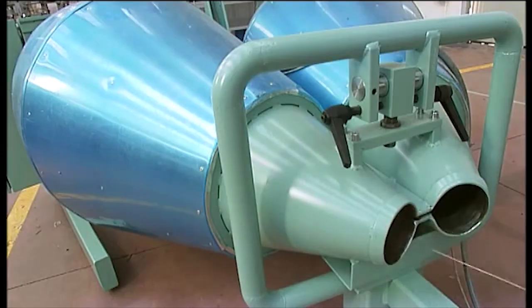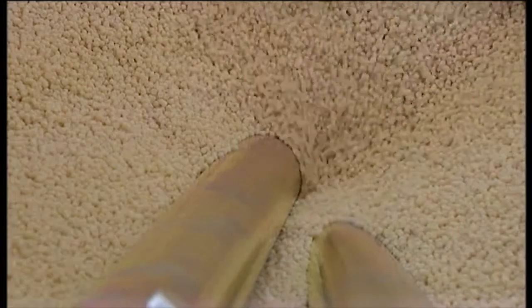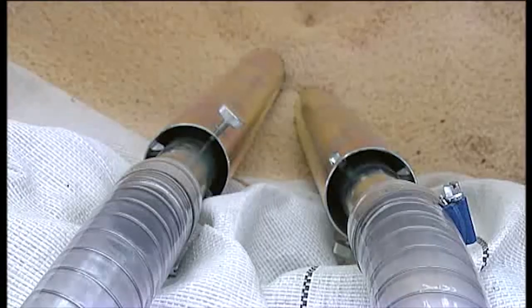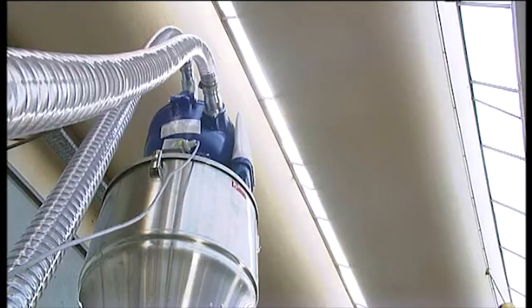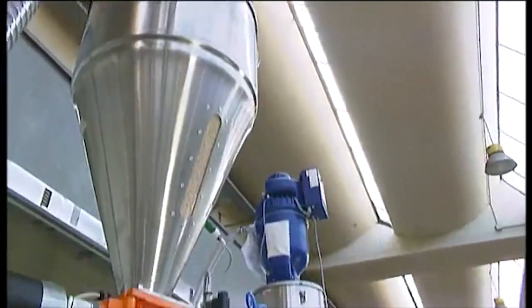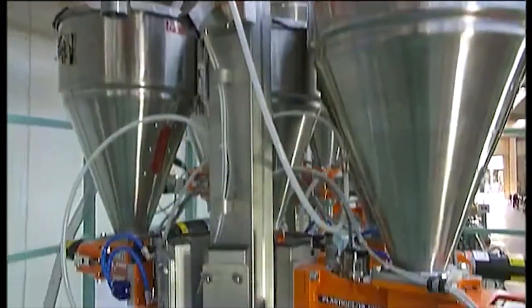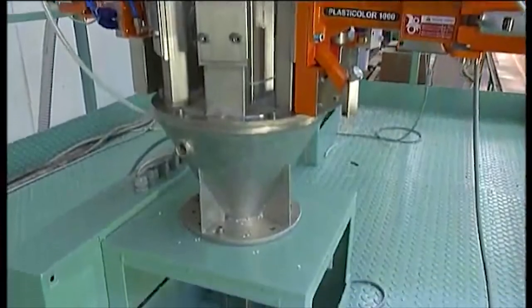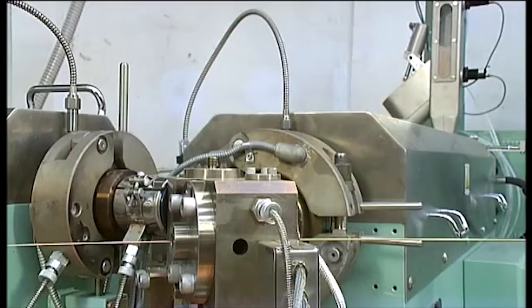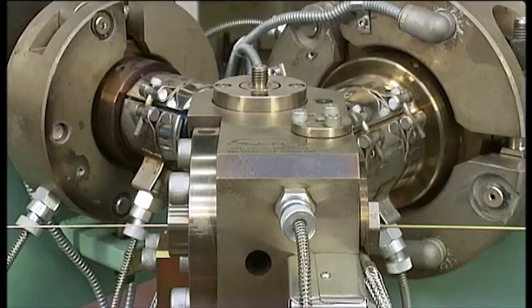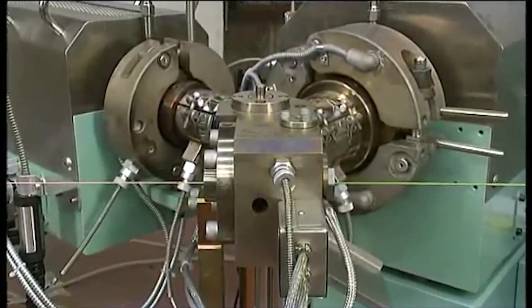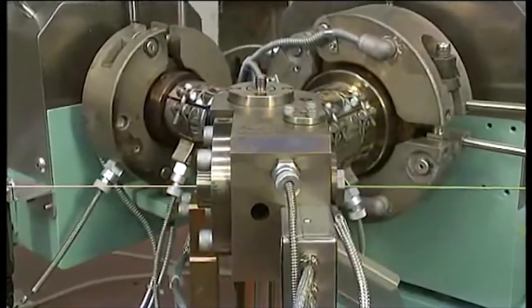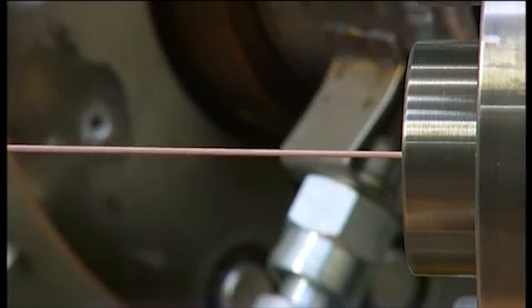The PVC insulation is done in a double-layer process, the first layer with virgin PVC and an outer layer, which is very thin and commonly called a skin, with color PVC. It is done to avoid the adverse effect of color pigment on the insulation resistance value of PVC, as the virgin PVC insulation has very good resistance.